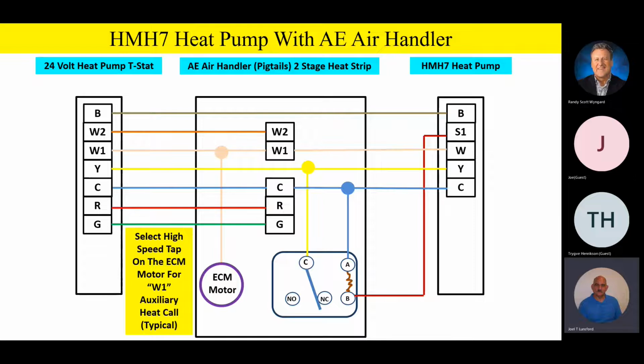Now, the reason we do that is we want to make sure we have adequate airflow, because the heat pump is going to be running, it's going to be in defrost, or we're having an auxiliary heat call, and you're going to have a heat strip running at the same time. So we want to make sure we have high airflow on that. So anytime we have a first stage W1 call, the ECM motor is going to be commanded to high-speed airflow. This is very typical, and more often than not, this is exactly how we see that.